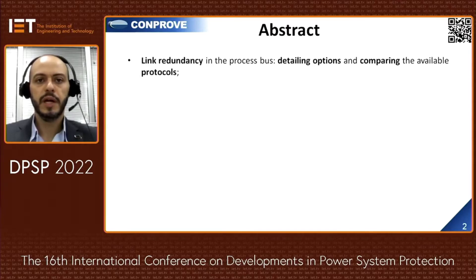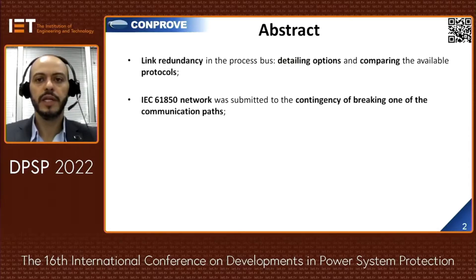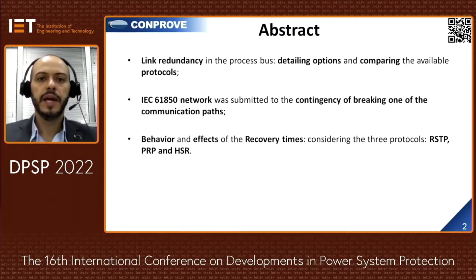This paper aims to approach Link Redundancy in the Process Bus, detailing the protocol options and comparing them. It was implemented an IEC 61850 network with Link Redundancy consisting of an IED and a test set simulating a merging unit. This network was submitted to contingencies of breaking one communication path. The behavior and the effects of the recovery time were evaluated and discussed over the three Link Redundancy Protocols: RSTP, PRP, and HSR.